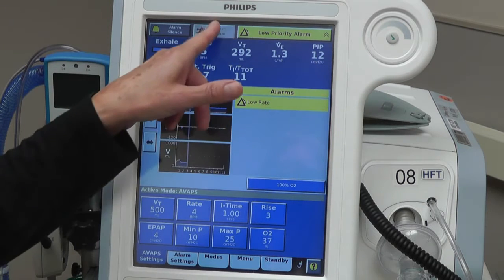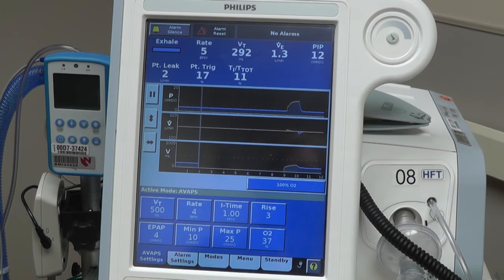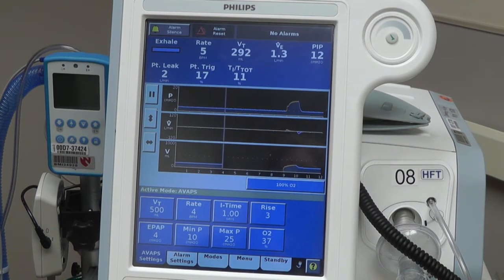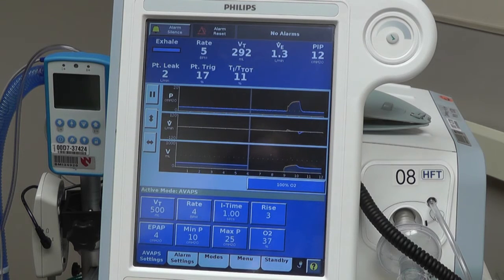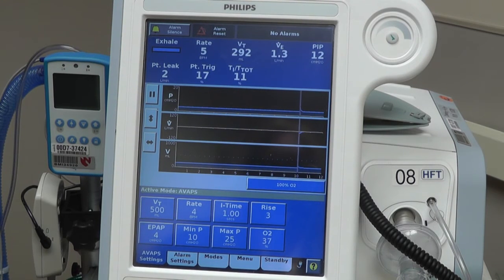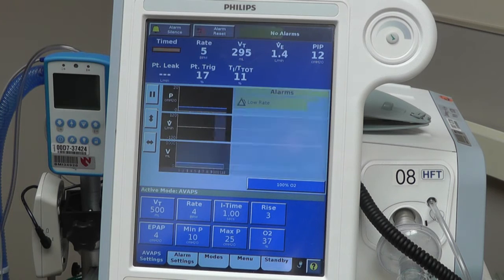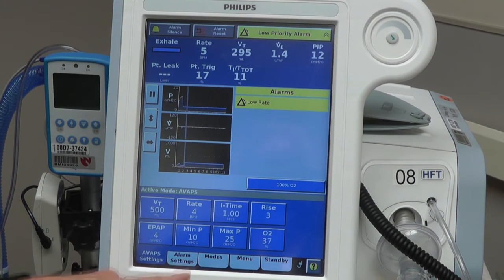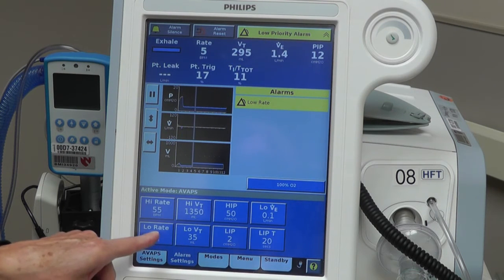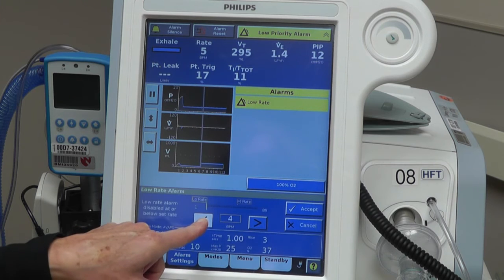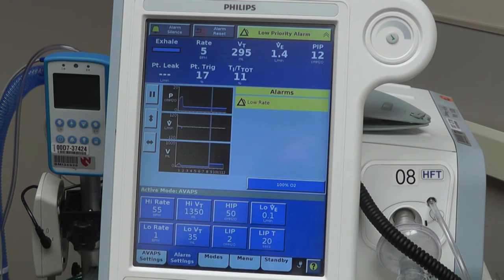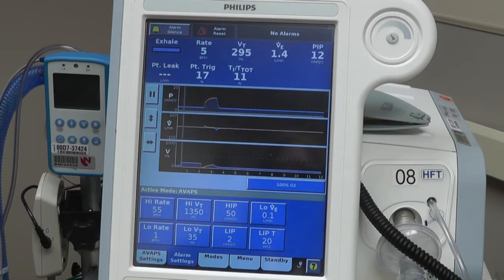Something else that might come up, if their mask is too loose, which often happens in our department, if you walk in and you see that the mask is on their forehead, of course adjusting the mask will solve a lot of alarms. A low priority alarm doesn't have to be solved right away, so you don't have to take them off the machine for low priority alarms. You can just call your respiratory therapist and we can come investigate what the problem is.